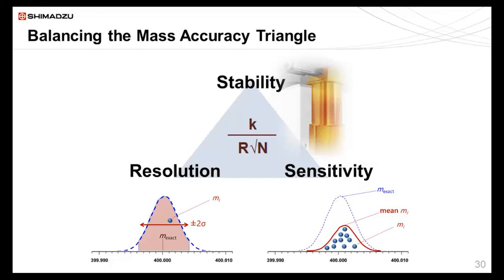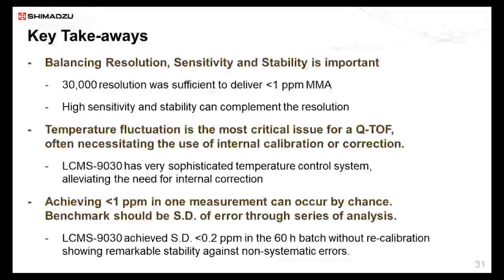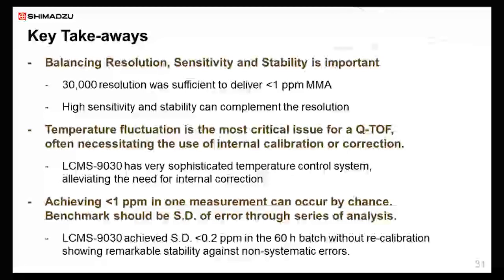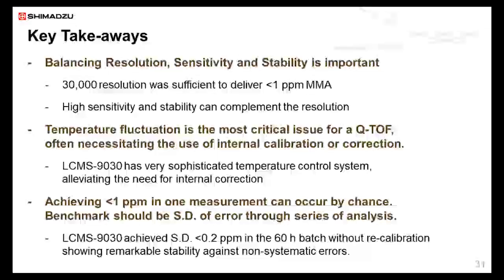So in conclusion, we've balanced the stability and resolution and sensitivity to achieve better than 1 ppm error in a stable fashion. So here are the key takeaways. Achieving good mass accuracy is a balance between resolution, sensitivity, and stability. And we've shown that 30,000 resolution was more than sufficient to deliver better than 1 ppm mass measurement accuracy. And this was achieved by high sensitivity and stability. Temperature fluctuation is the most critical issue for any Q-TOF, often necessitating the use of internal calibration or correction. But we've addressed this quite nicely, and we've alleviated the need for internal correction.